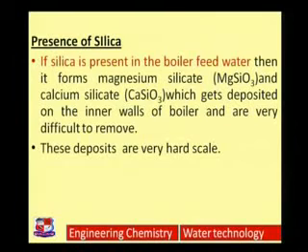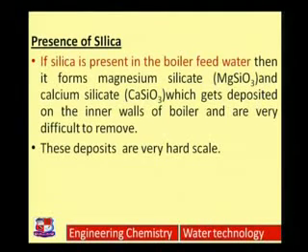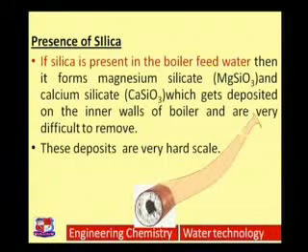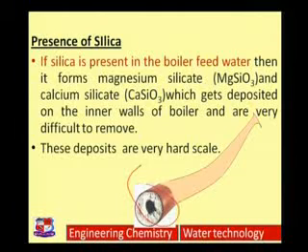Besides that, if silica is present in the boiler feed water, it may react with the hardness-causing salts of calcium and magnesium, converting them into magnesium silicate or calcium silicate, which get deposited on the inner walls of the boiler. These are very difficult to remove — they are very hard scales. As shown in the picture, the scale is deposited on the inner wall of the boiler as a coating.